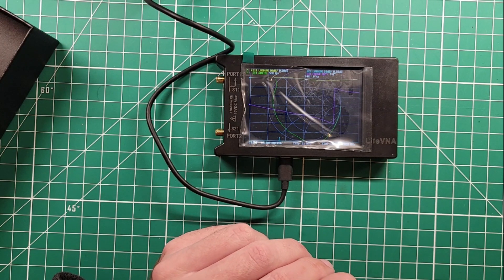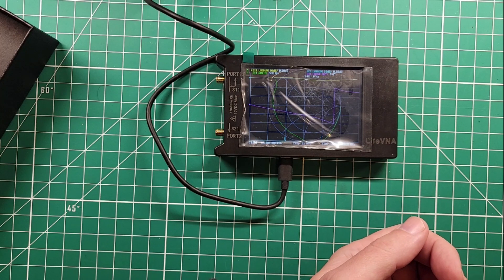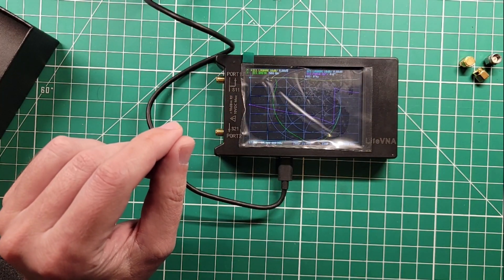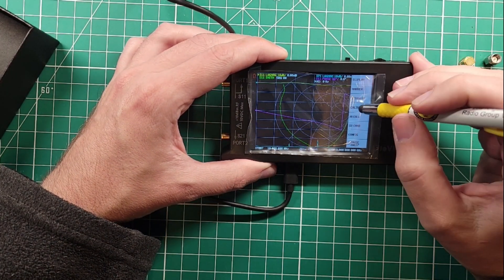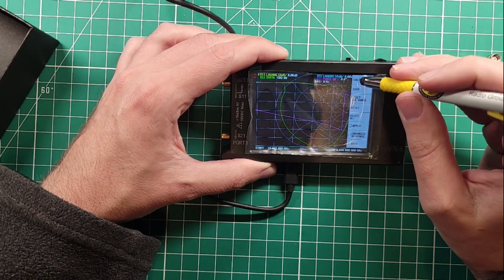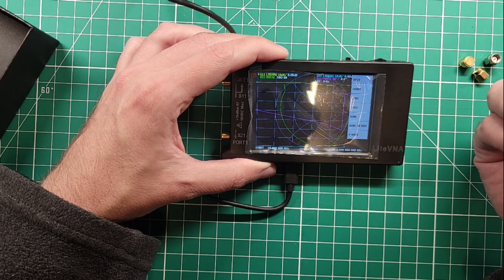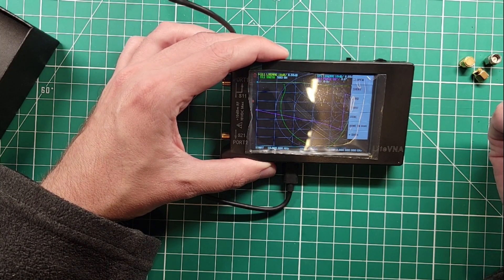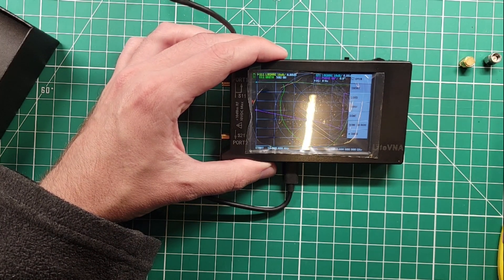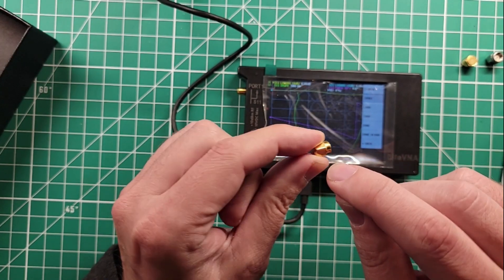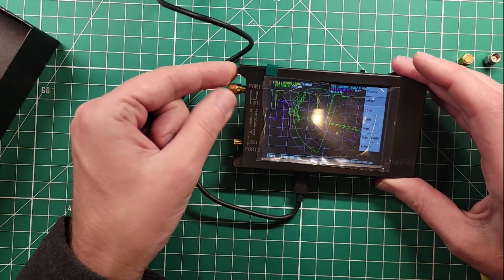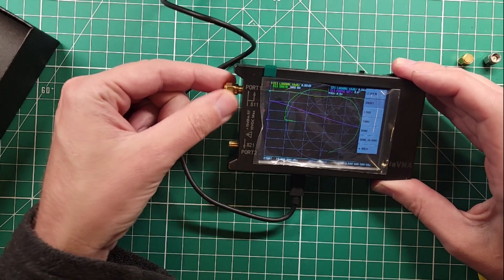Okay. So I'm going to pull out my load standards. And we'll check out what a calibration looks like. Because that's something that people do all the time with these things here. So let's do calibrate. And we want to calibrate. And we want to calibrate the open. So there's nothing on which is the same as doing an open. That has finished. That seems to take about the same amount of time. We're going to use the short. This is connecting the center conductor to the outside. And that's a short. That's pretty cool.